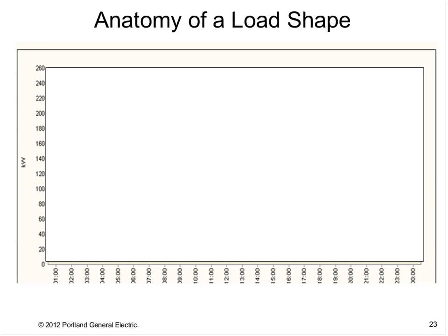So I'm going to draw what my load shape would look like if I had a building like that. It'll be a little more explanatory once I'm done drawing. Like I said, I had a base load of 100 kW, and then around 5 o'clock in the morning, my lights come on, and then around 6 o'clock, the outdoor lighting shuts off, and then around 8 o'clock, we ramp up, people start coming in, and the HVAC is humming. And then once everybody's there during the day, it tends to flatten out for a few hours.